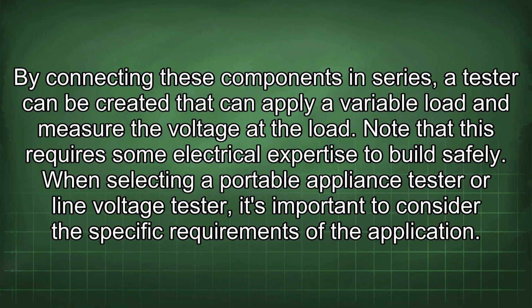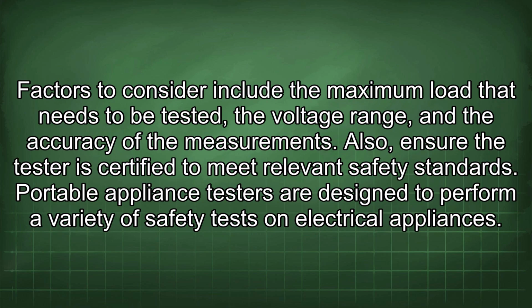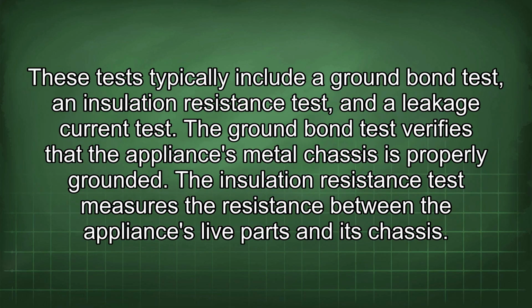When selecting a portable appliance tester or line voltage tester, it's important to consider the specific requirements of the application. Factors to consider include the maximum load that needs to be tested, the voltage range, and the accuracy of the measurements. Also, ensure the tester is certified to meet relevant safety standards. Portable appliance testers are designed to perform a variety of safety tests on electrical appliances. These tests typically include a ground bond test, an insulation resistance test, and a leakage current test.